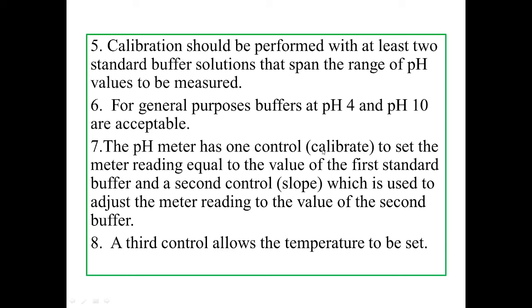The pH meter has one control button to calibrate. Using the calibrate button, set the meter reading equal to the first standard buffer. Our first standard buffer had pH 4, so set the meter reading to 4. Then remove the electrode, rinse the electrode, and then dip it into the second buffer.